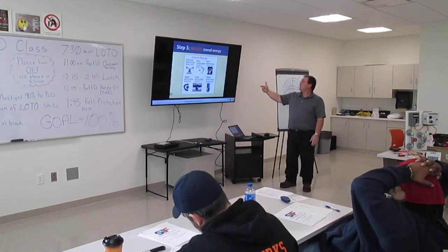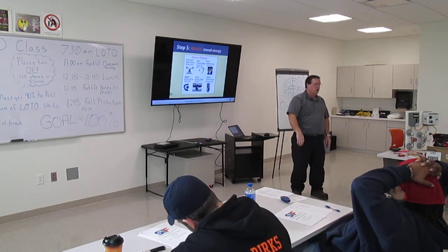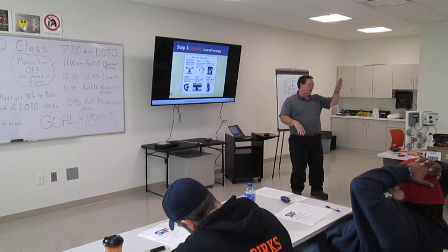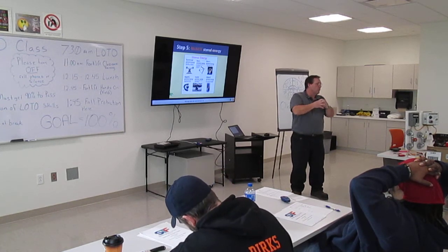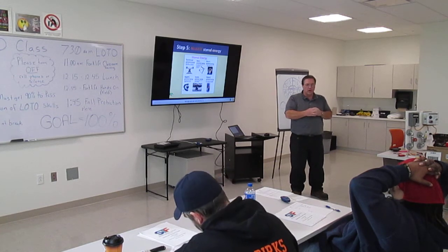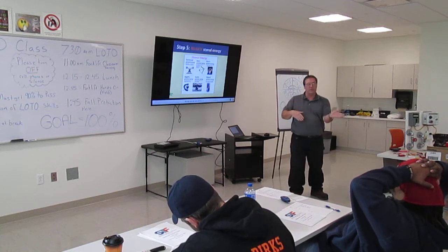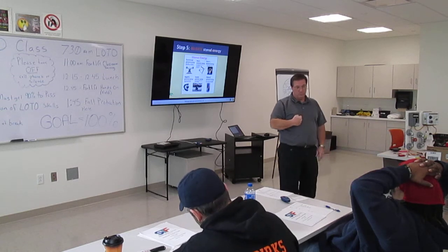This is releasing stored energy. So at this point, if there's a load up in the air, you can let it down. If you can't let it down, you've got to block it. Out on the dock plates, they're all hydraulically lifted up. All the electrical controls, all the pump, all the hoses, everything are under the dock plate. You can't work on it without that dock plate being straight up, ready to fall on your head. So there's a steel bar you flip up, you put a pin through, you put your lock on it. That dock plate doesn't fall on you.